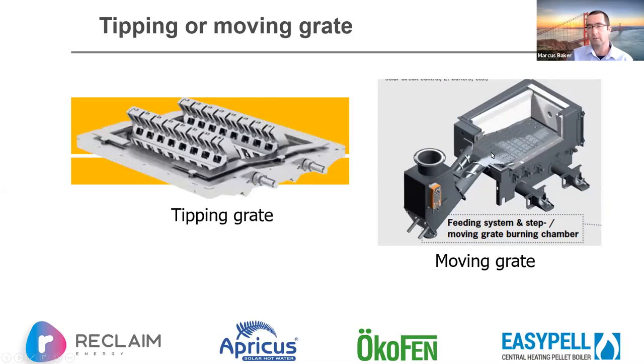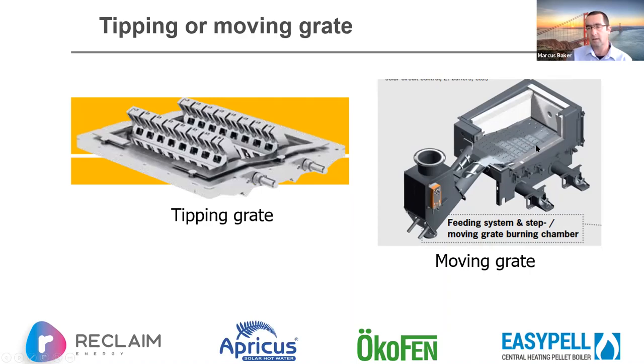These are different approaches to the same question. You need to be aware of maintenance requirements around different types of grates, because if things go wrong they tend to go wrong in this area — clinker getting stuck and stopping the grate from closing. Ensuring combustion is well monitored and fuel quality is addressed is key. Getting an understanding from the supplier about maintenance needs and system robustness is important.